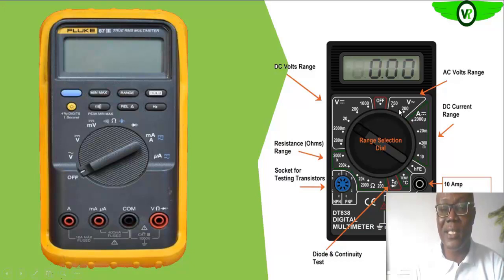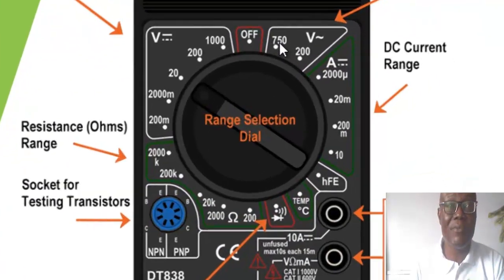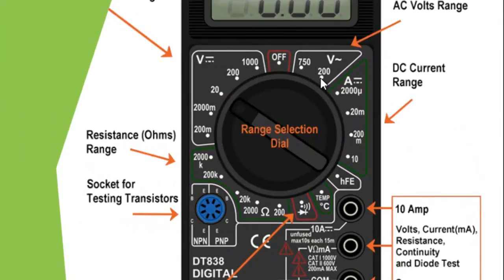When testing, maybe when your circuit is active, maybe you are testing voltage, it is preferable, if you are not too sure of the circuit voltage, to test with the highest range. Assuming you are testing an AC circuit, the highest range here is 750, so it is advisable you test with 750. When you notice it is less than the other range, you can decide to reduce it or leave it at that upper range. It is the same with the DC voltages and current ranges.